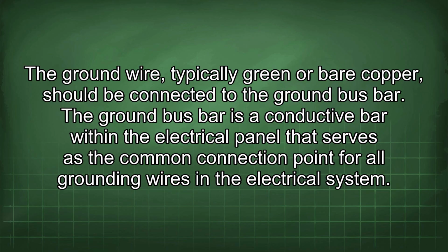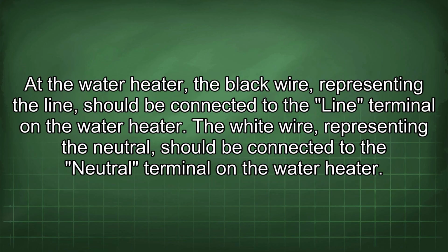The ground wire, typically green or bare copper, should be connected to the ground bus bar. The ground bus bar is a conductive bar within the electrical panel that serves as the common connection point for all grounding wires in the electrical system. At the water heater, the black wire, representing the line, should be connected to the line terminal on the water heater. The white wire, representing the neutral, should be connected to the neutral terminal on the water heater.